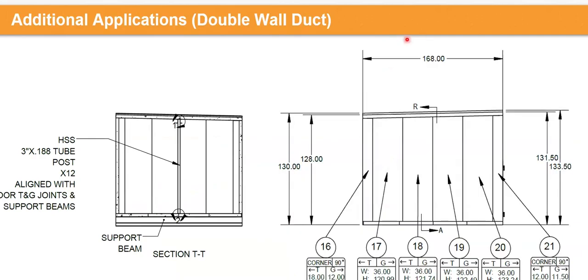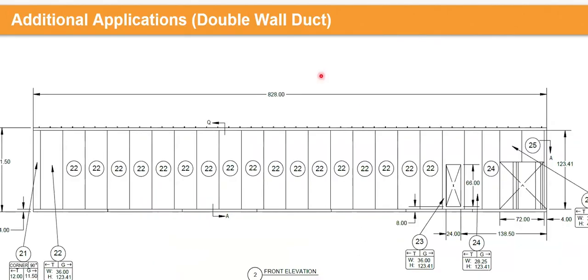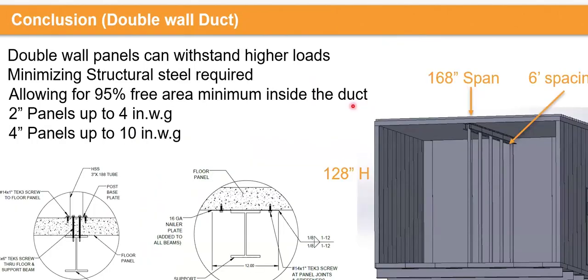If you look at the dimensions, we have 168 inches wide. We can do this in one single panel to be able to make sure that you have the highest free area available. If you look at the width as well, this is as long as 828 inches wide, which is a wide span.